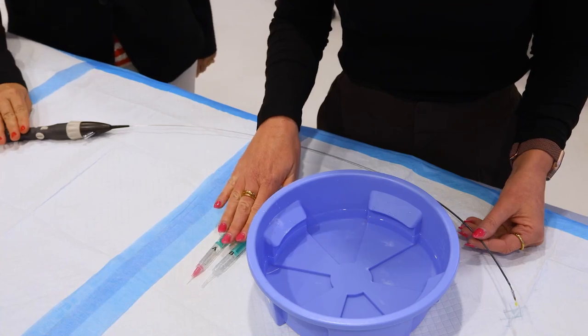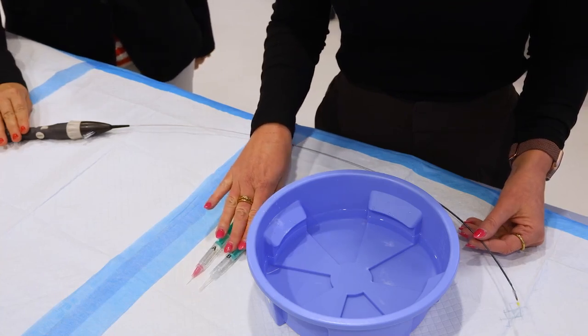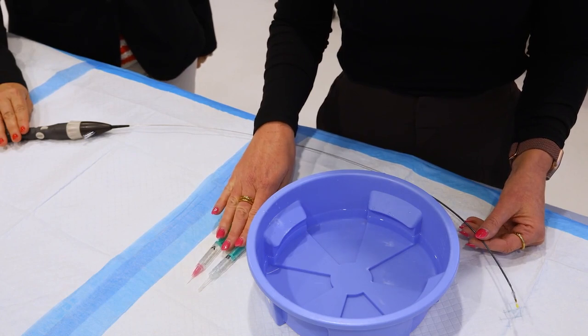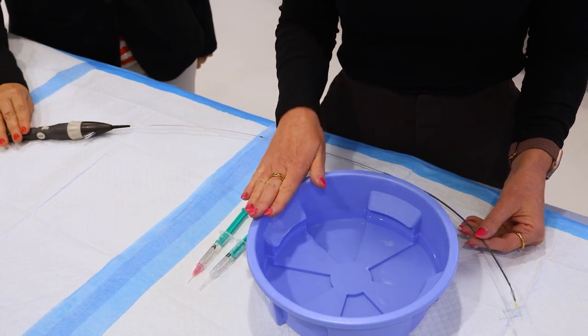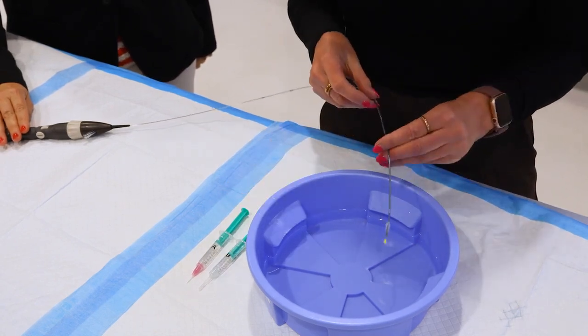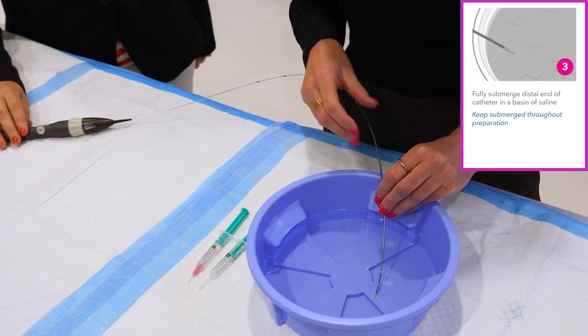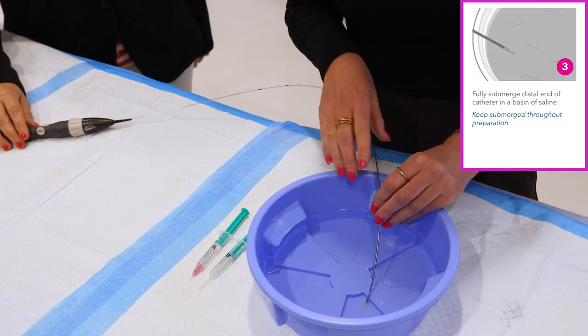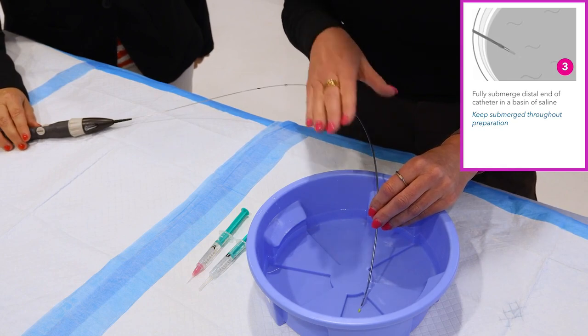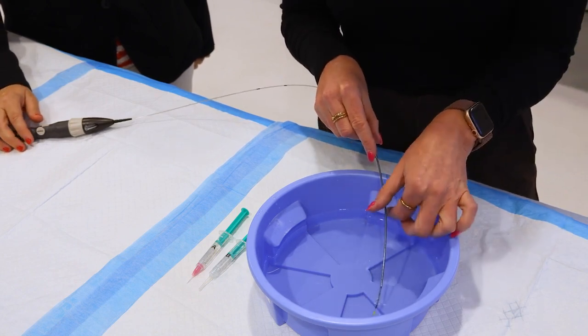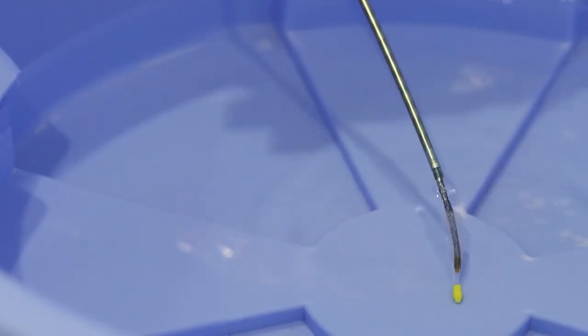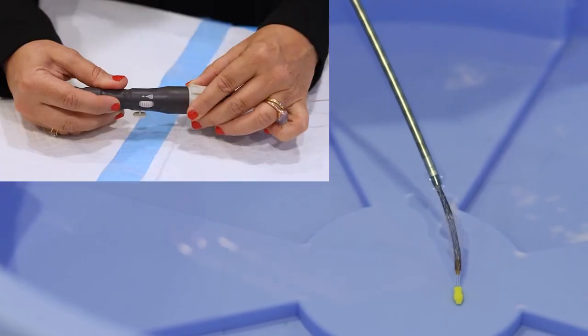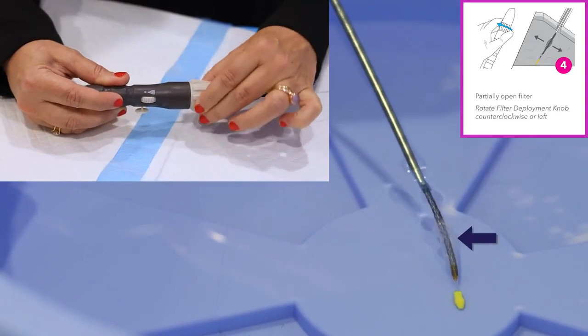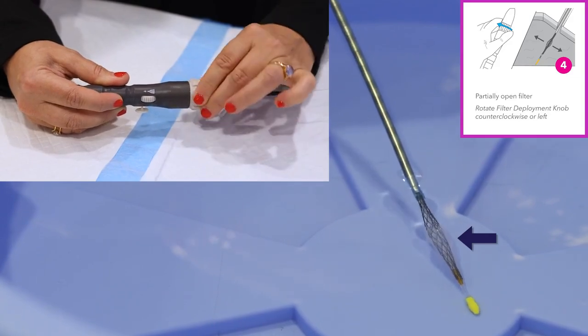With our syringes already filled, syringe A and syringe B are both filled with sterile saline already. We're going to take our saline basin and we're going to fully submerge the distal end of our device, making sure that the filter in its entirety is submerged in saline. With the distal end fully submerged in saline basin, you partially open the filter by rotating the filter deployment knob on the handle counterclockwise.